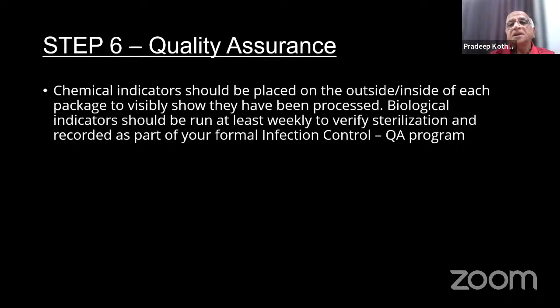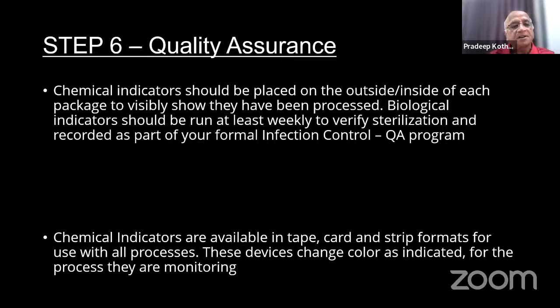The next step is quality control. Chemical indicators, we all are aware of. They should be placed inside as well as outside of the packages so that we know they are sterilized properly. Chemical indicators are available in tape, card and strip formats for use with all processes. These devices change color as indicated for the process they are monitoring. Record keeping of this is very important, separate for autoclave, separate for ETO, so that we are very sure that instruments are sterilized properly.